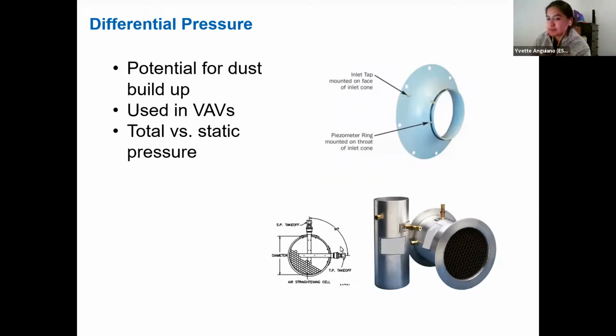In terms of the pitot tube application, it's got this honeycomb layout here that you can see, and we're using that honeycomb layout to keep the airflow laminar through the device. The pitot tubes are located inside this device, and they're measuring the total pressure on the upstream side of the airflow, and the static pressure on the downstream side. The difference between those pressures gives you the velocity pressure, which is directly proportional to the airflow. And then, as I explained before, the con of this device is this honeycomb layout, because it acts as a filter and collects a lot of dust, requires a lot more maintenance, and could fail due to that lack of cleaning.